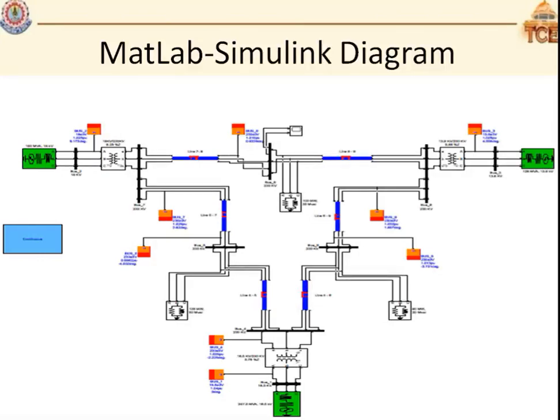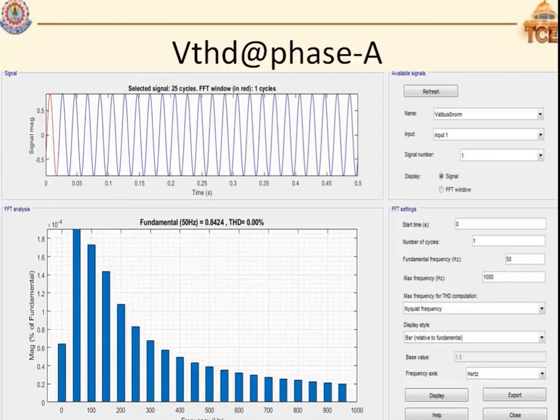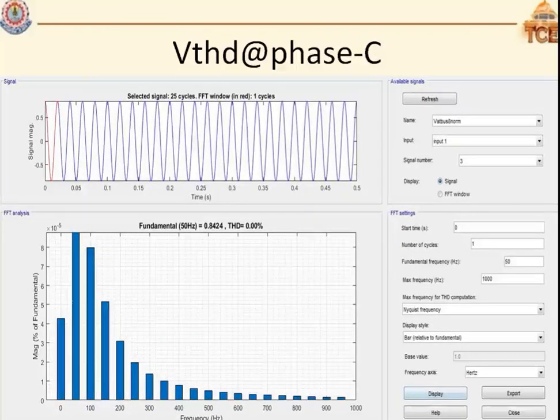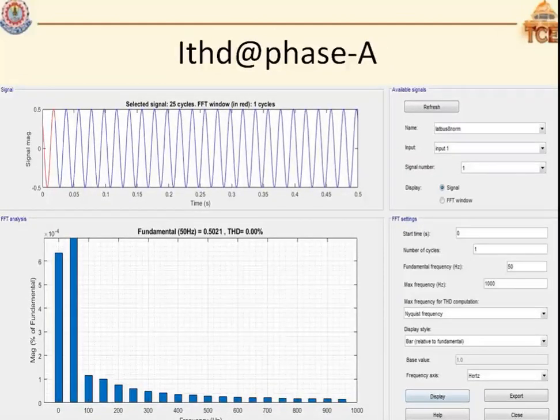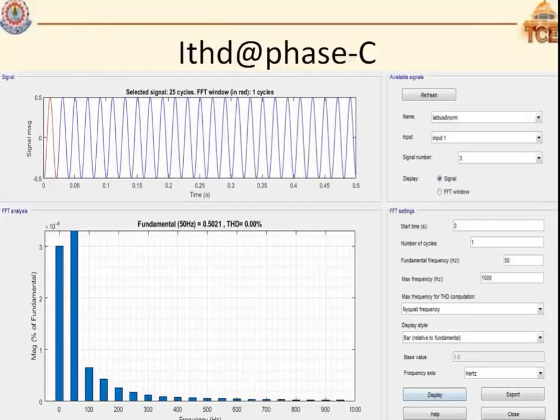Here we can see the transformers and 3 kinds of load, and all 3 loads are linear loads, not non-linear loads. In the FFT analysis at the PCC, due to the linear load, there were no power quality issues in the grid. The voltage THD and current THD are 0%. In real time there will be a little amount of THD, but in MATLAB it is a steady state case, so a linear load indicates only 0 THD. These are phase B and phase C. For the 3 phases, the voltage THD was measured. This is the current THD for phase A, phase B, and phase C.